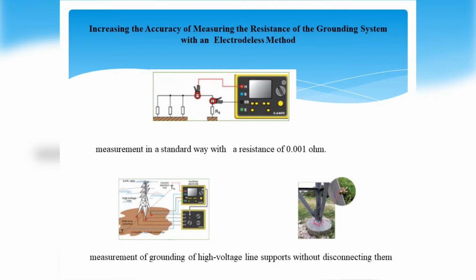In particular, instruments for measuring the resistance of the grounding device, in addition to the performance of the climatic conditions of operation, require the specific placement of current and potential electrodes, metal pins jammed into the ground, relative to the investigated ground contour, depending on the geometric dimensions of the circuit, and set the maximum permissible earth resistance of the electrodes themselves, depending on the resistivity of the soil in which they are placed. In the central part of any city, where the saturation of buildings and underground utilities is high, solid asphalt or concrete, the application of these devices becomes impossible.